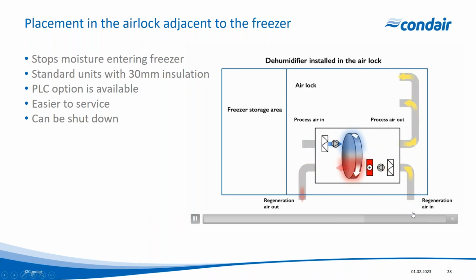And we've still got to get rid of the moisture, so we have regeneration air coming in from external, going in over a filter and a fan, over our heater, and then hitting our desiccant, drying it out, and we're taking that regeneration air out. Now, the quite interesting thing about doing it this way is that if we dehumidify the air in the chill store, when they open the door to the freezer store, the air is much drier, so the potential for ice forming on the evaporator in the freezer store is vastly reduced because we've done the dehumidification in the chill store. So just by doing the chill store, you're reducing ice buildup in the evaporator in the chill store, but also concurrently reducing the ice buildup in the freezer area.